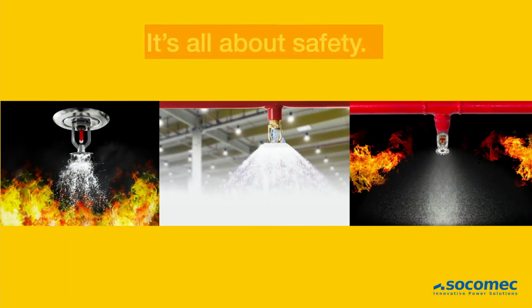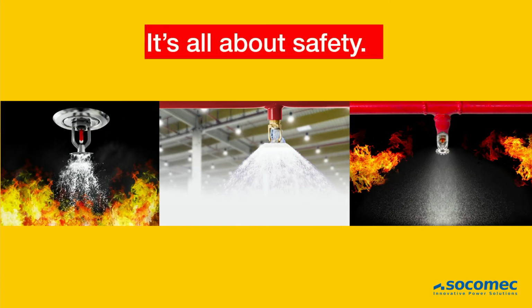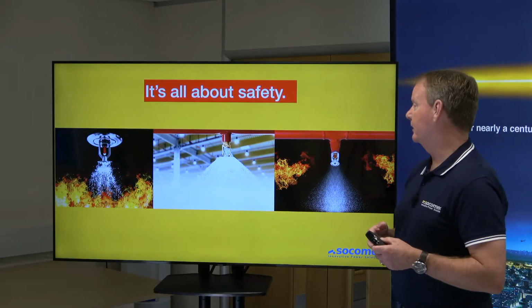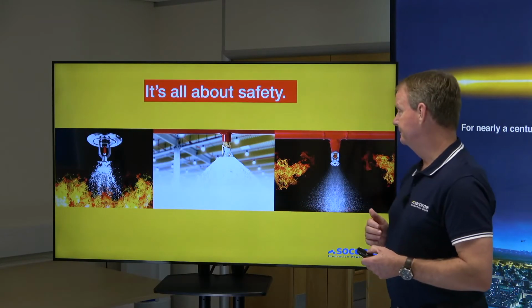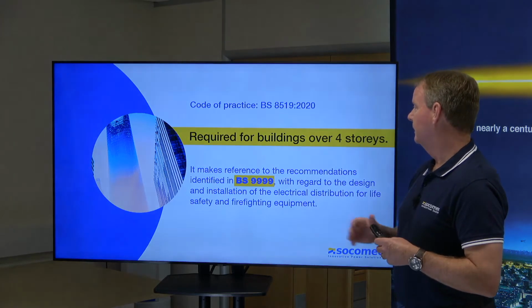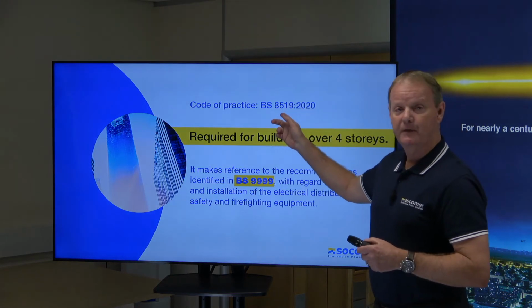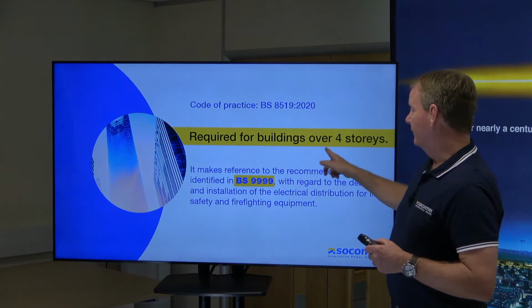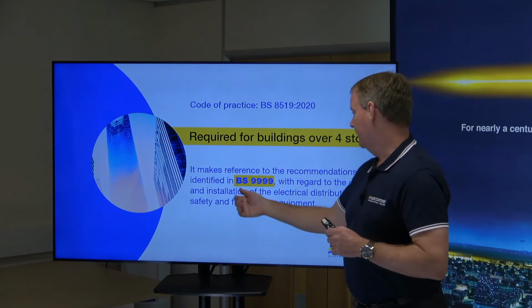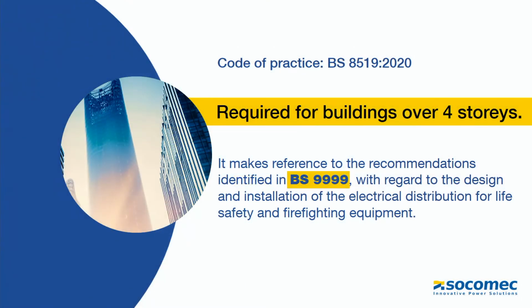So what we are talking about here, it's all about safety. Okay, so we've got fire sprinkler systems here, but also it could be fire pumps, smoke extraction, etc. So, under the Code of Practice, BS 8519/2020, required for buildings over 4 stories high. It does make reference to BS 9999 with regard to the design, installation, low voltage electrical distribution for life safety. So they actually mentioned each other, BS 9999 and 8519.